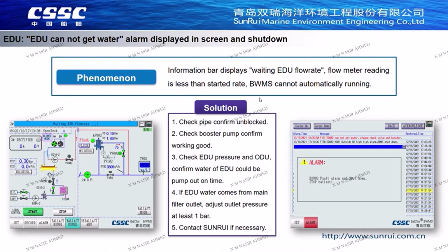Usually, the alarm is delayed for about 1 minute. If the EDU still cannot reach the start flow, it will trigger the alarm and shut down. Different types of systems have different startup EDU flow rates. Please refer to the manual book.